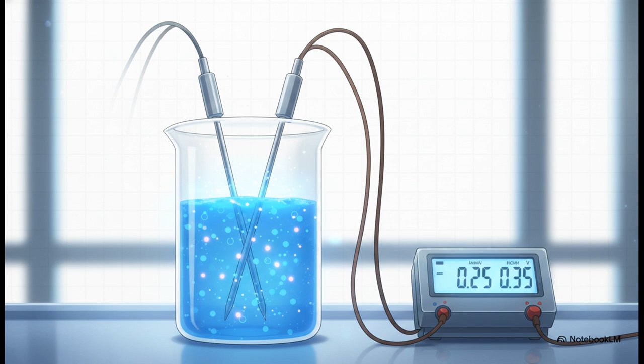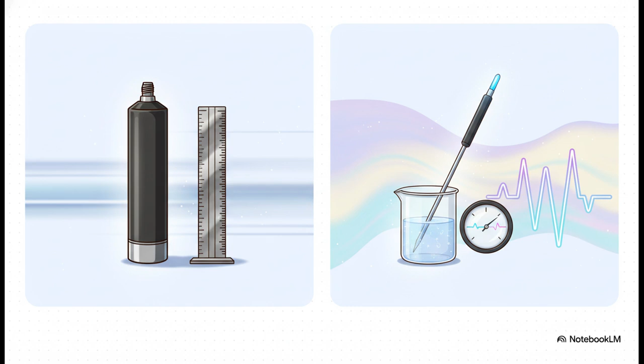Now, this isn't just some happy coincidence. It's all governed by a famous piece of science called the Nernst equation. Look, we're not going to get bogged down in the math here, but the crucial takeaway is that this equation is the rule book. It gives us the exact, predictable link between the voltage you can measure on a meter and the concentration you're actually trying to find. So how do we actually do this? Well, you need a two-part toolkit. First up, you have the reference electrode. I want you to think of this as your unchanging yardstick. Its whole job is to provide a perfectly stable, constant voltage, no matter what. Then you have the indicator electrode. Now this one is the sensitive probe. Its voltage changes depending on how much of your target ion is in the solution. And the difference in voltage between that steady yardstick and the changing probe, that's your answer.